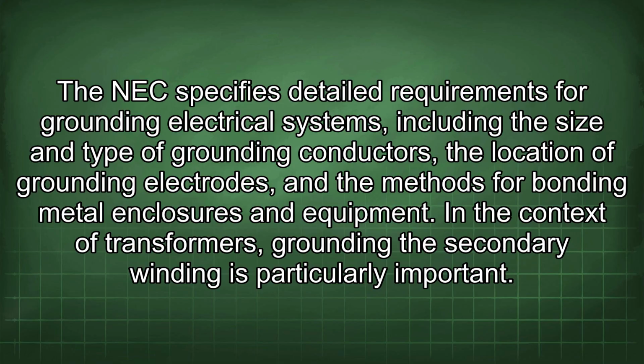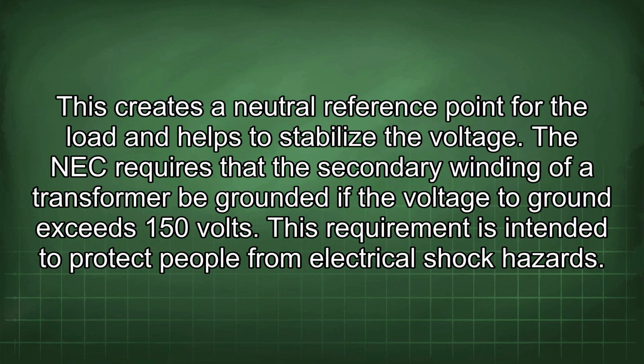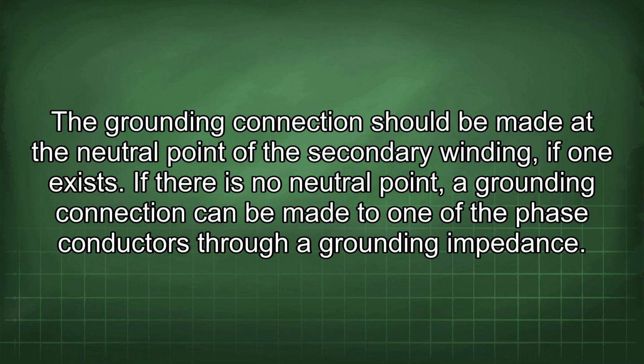In the context of transformers, grounding the secondary winding is particularly important. This creates a neutral reference point for the load and helps to stabilize the voltage. The NEC requires that the secondary winding of a transformer be grounded if the voltage to ground exceeds 150 volts. This requirement is intended to protect people from electrical shock hazards. The grounding connection should be made at the neutral point of the secondary winding, if one exists. If there is no neutral point, a grounding connection can be made to one of the phase conductors through grounding impedance.